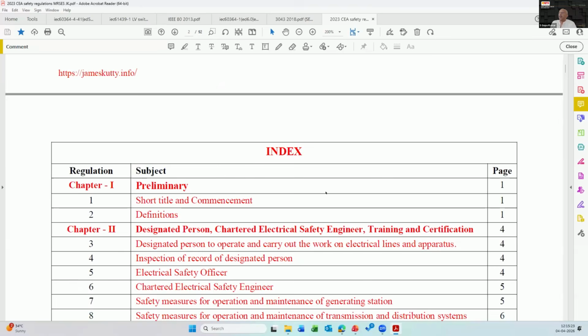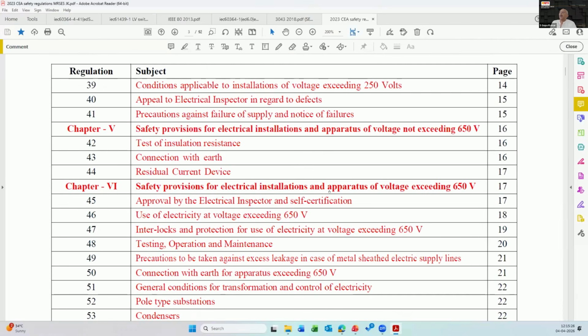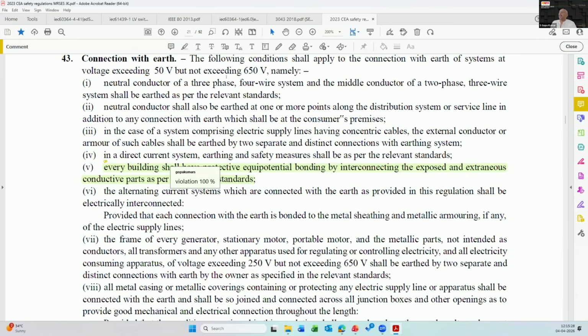CEA regulation number 43. This is the latest regulation. I'm showing regulation 43 of the 2023 regulation. Neutral conductor of a three-phase four-wire system and the middle conductor of a two-phase three-wire system shall be earthed as per the relevant standard. Neutral conductor shall also be earthed at one or more points along the distribution system or service line, in addition to any connection with the earth which shall be at consumer's premise. Please note that this is for the neutral conductor.